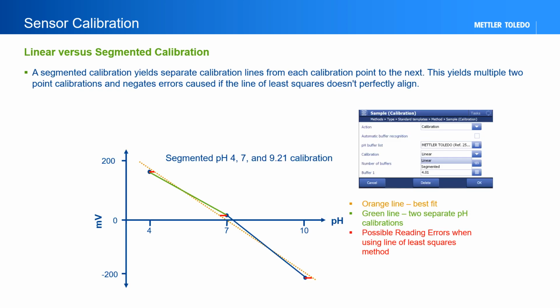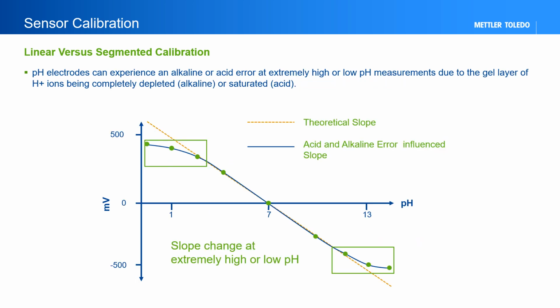The segmented calibration in METTLER TOLEDO pH meters and titrators is preferred to avoid the possible errors that could arise from a linear calibration. A segmented calibration yields separate calibration lines from each calibration point to the next. This yields multiple 2-point calibrations and negates any errors caused if the line of least squares doesn't perfectly align with all the calibration points. In extremely high or low pH solutions, electrodes can experience an alkali or acid error. This is caused by either too many hydrogen ions present in solution or too few hydrogen ions in and on the glass pH bulb. Near these pH values, segmented calibrations are most useful as the calibration line deviates from a theoretical straight line.